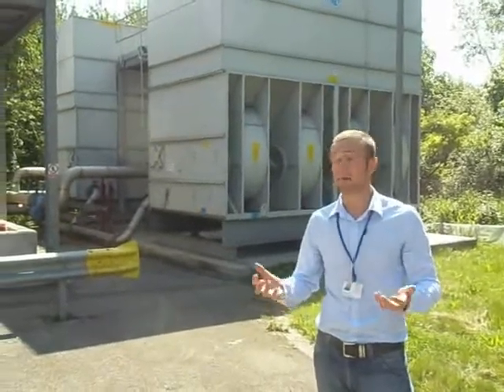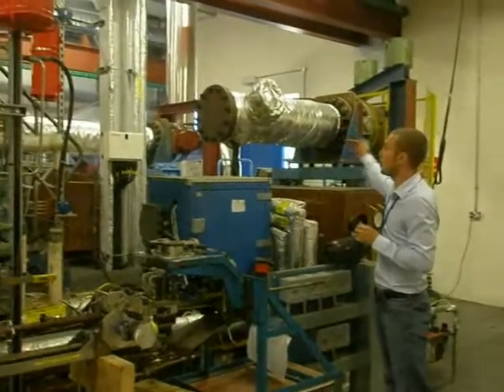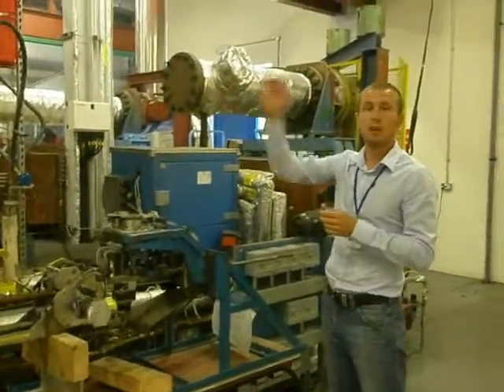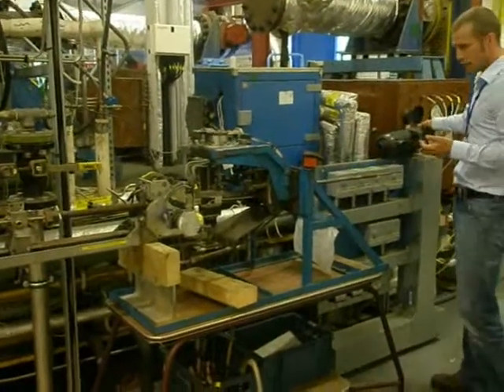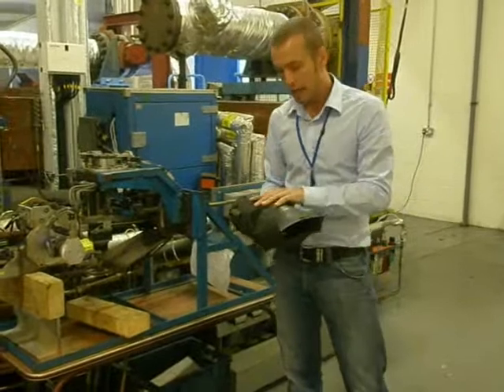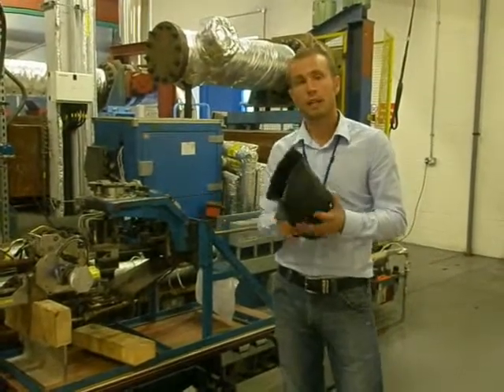We're actually back in the rig room now, back with the sector combustion rig. We've actually seen where the main combustion air is coming from — it's coming in through this pipe here, travelling in that direction. So we have our 16 bar air, possibly 5 kilograms per second, and 850 to 900K coming into this pipe. This open space here is actually our working section, and our test rig would actually go in there. What we have in front of us is a traversing probe. On this rig we would typically have a combustion can like this, and what this probe enables us to do is take gas samples from within the combustor when we're running at full load. This is really important to gas turbine manufacturers who are trying to design actual combustion chambers and are using computational fluid dynamics software — they need real-world data to validate that software, and we're actually providing that.